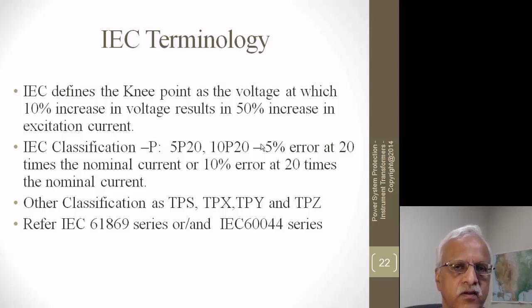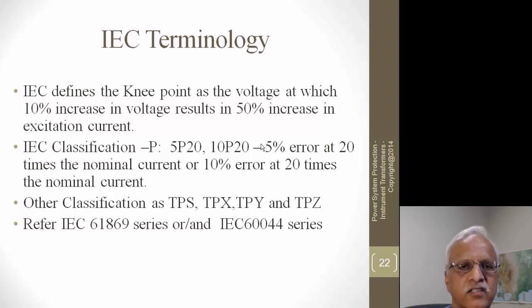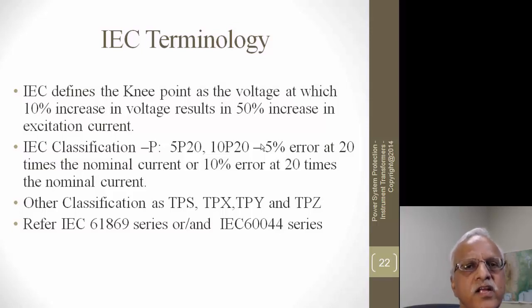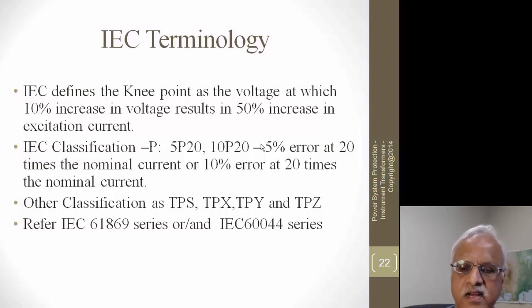IEC has other classifications: 5P20 means five percent error when the current is 20 times the nominal secondary current; 10P20 means 10 percent error at 20 times nominal current. There are more detailed IEC classifications — TPS, TPX, TPY, and TPZ — which are not covered here in detail; please refer to the IEC standards documents for explanation.